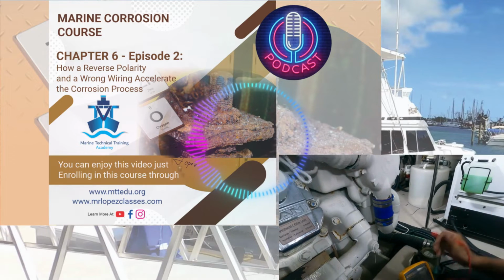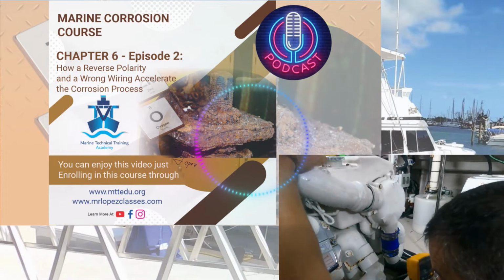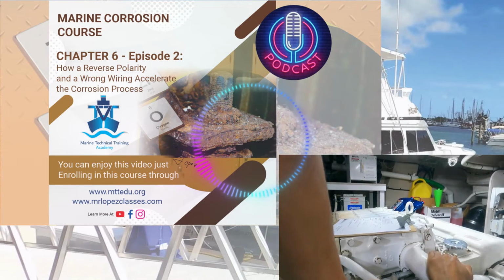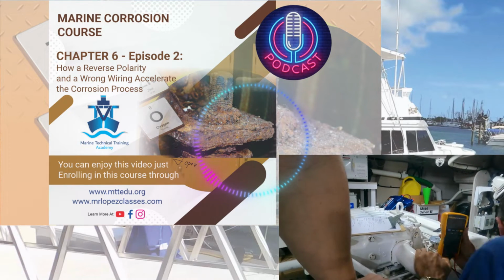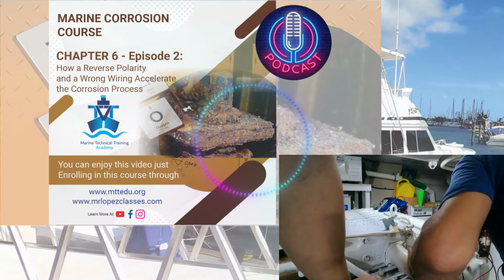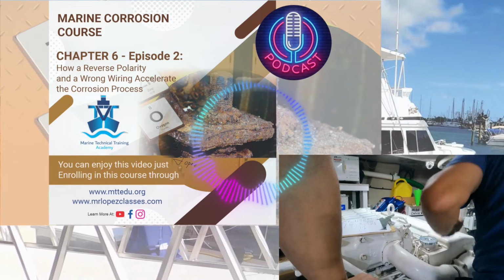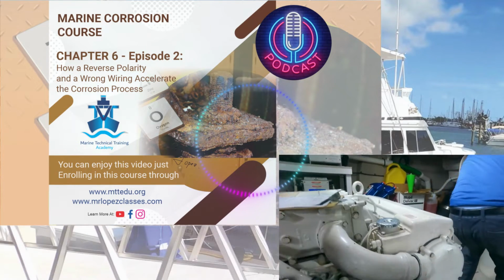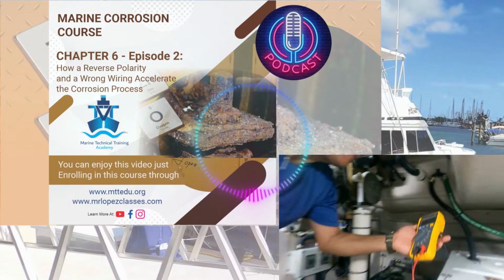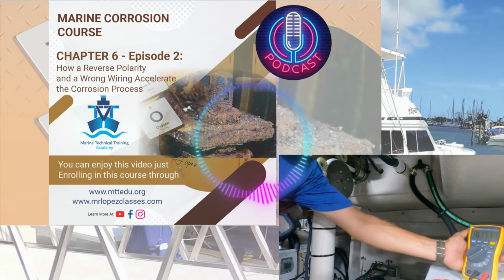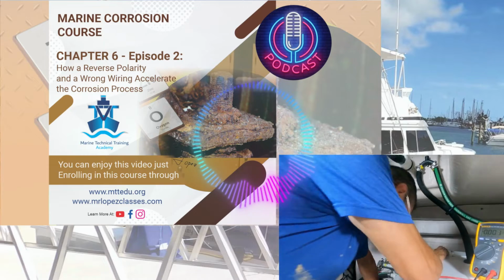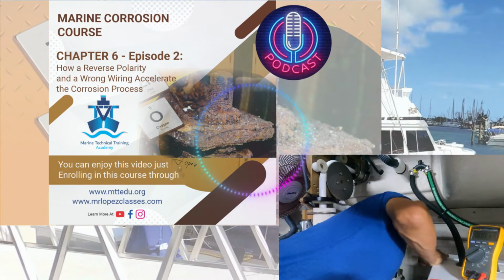Right now, the outlet is wrong. The neutral and the hot is switched. And I have two blowers running 24 hours. But those blowers, the return, remember, is always through the neutral. And right now, the neutral is hot and the hot is neutral.